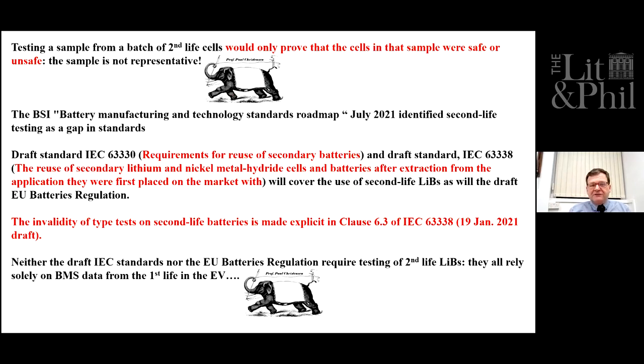The invalidity of type tests is made explicit in IEC 63338, this draft code. None of these tests, nor the new draft EU batteries regulation, actually require testing of second life batteries to prove their safety - they all rely on the battery management system. There are problems here because the information contained in the battery management system is intellectual property, and it's not at all clear that electric vehicle manufacturers will want to release this IP to a third party, the repurposer - elephant in the room.